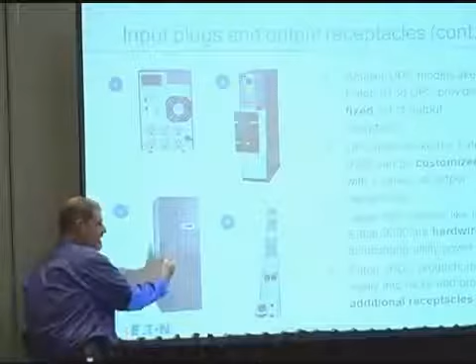When I'm running a circuit into a rack, let's say in a given 42U rack, 19-inch enclosure, I have 20 devices that I need to power up. Does it make sense to run 20 circuits into that cabinet? No. Right? I'll run one three-phase 30-amp circuit into the cabinet, and then I'll use a vertical power strip or an enclosure PDU or an ePDU to distribute the power. So I have 30-amp three-phase coming in. I've got 3 circuits, phase A, phase B, phase C, with the appropriate plugs I need. So I use the distribution, and that helps me whittle through that minefield of options that I have available.